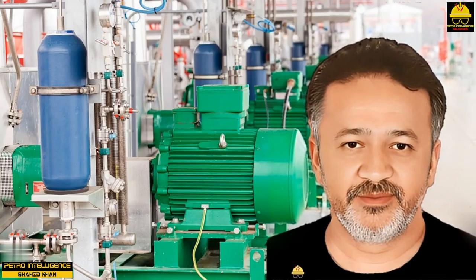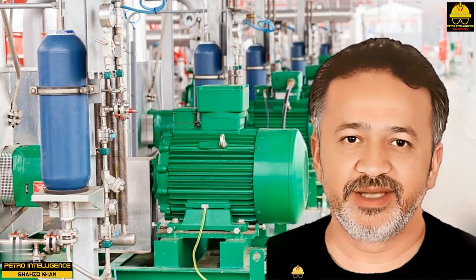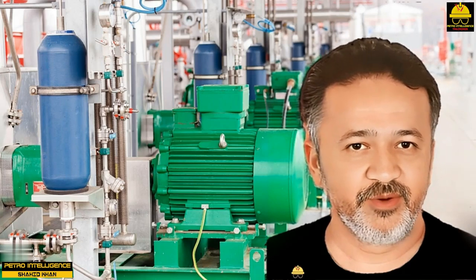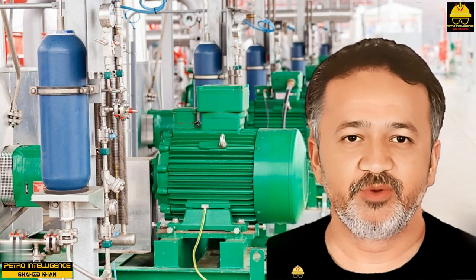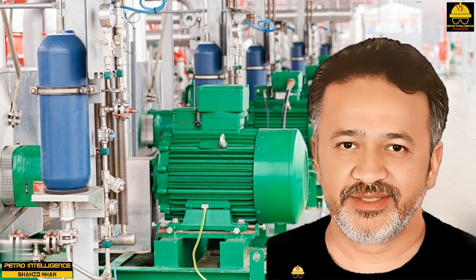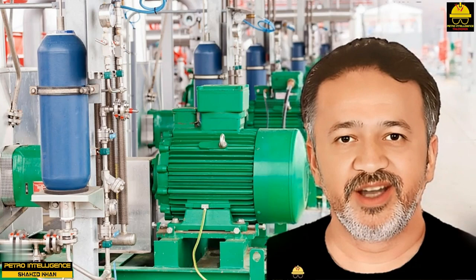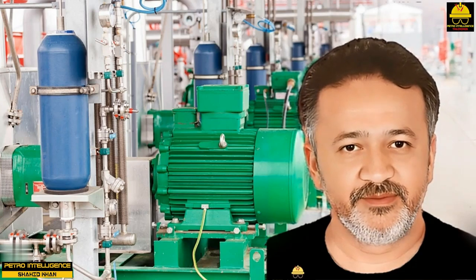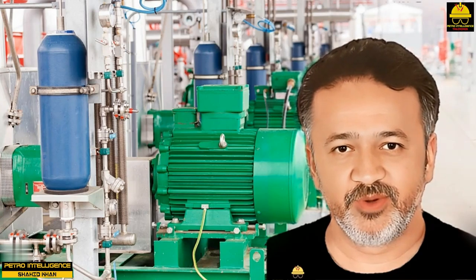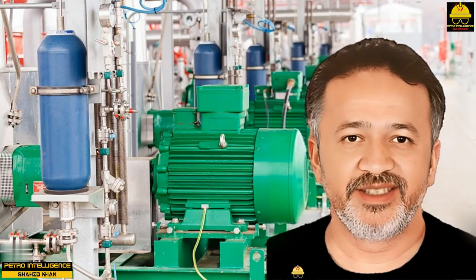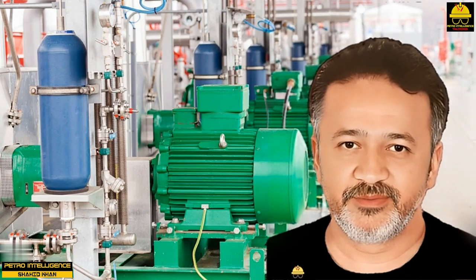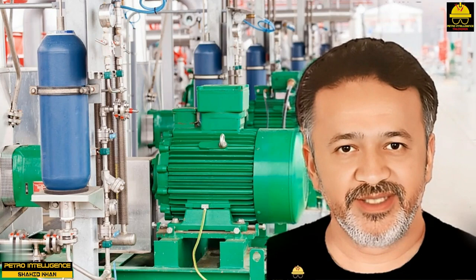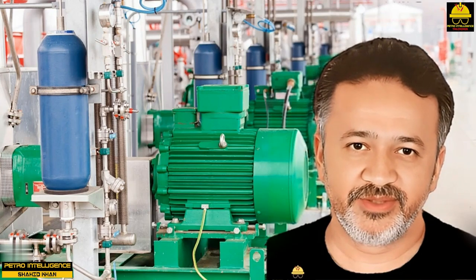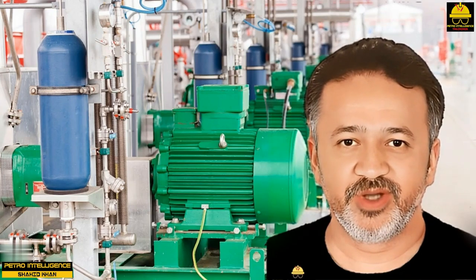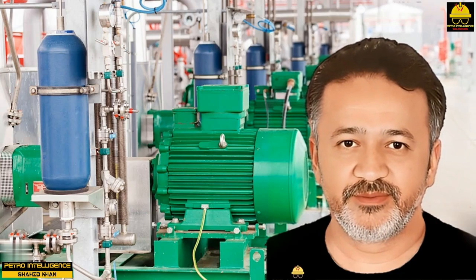Rotary pumps. Rotary pumps are PD pumps that transfer liquids by using a rotary motion. The drive shaft turns the rotary elements inside a leak-tight chamber that has a defined inlet and outlet. Engineering design requires close running clearances between the rotating elements and chamber wall. Rotary pumps have very little internal slip. This type of pump is the most widely used positive displacement pump.